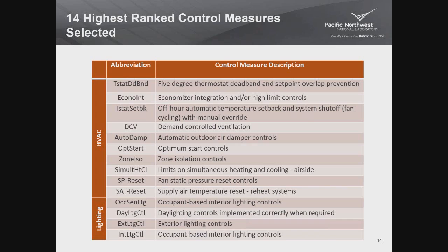Static pressure reset, another one for those same systems. The fan speed on those variable air volume reheat systems is controlled by a static pressure sensor in the ductwork. There's ways of adjusting that static pressure set point so that you can reduce fan energy automatically by the position of the dampers, what zones are in heating and cooling, and how much airflow is needed. Overall, with some smart logic, the static pressure set point can be reduced, and fan power can be reduced as well.